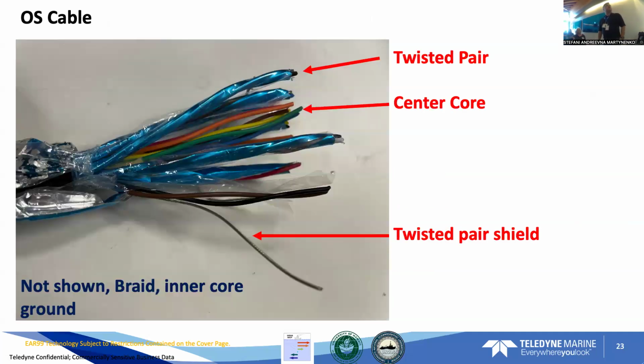And this is what it all looks like kind of close up. You have your twisted pairs, you have your center core. Then the twisted pair actually has an interconductor shielding. There's 2 of them here. You'll notice there's the shielding around the actual rubber portion of the cable that protects it. Then there's this hard inner shielding, and there's a ground that's part of that as well, along with your twisted pairs and your center core. Really fun system to have to terminate.